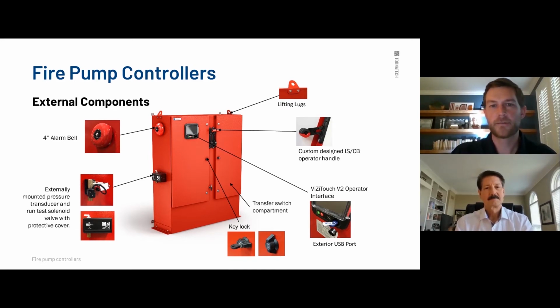External components again. This time, this is the controller with the isolation switch. So everything is basically the same bell, same externally mounted wetted parts, same ViZiTouch. And actually, if you notice on the transfer switch side, we don't have a screen. There's no data or anything on that side. That's just the separate barriered housing for the transfer switch that's required. But all of the information is going to be tracked right here in the ViZiTouch. So you don't have two screens to look at. When we have transfer switch, the ViZiTouch is monitoring the transfer switch as well.